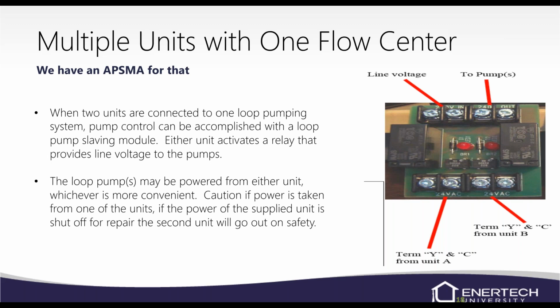Now, let's say that unit A is the one that's supplying the high voltage to the pump sharing module. If unit A goes down and you're out there working on it, and you kill the high voltage power, and then the second unit faults out on flow, well, that's because it's lost the high voltage and it's not turning your flow center pump on. So if you're working on one, it could actually affect the other unit as well. So just keep in mind that if you do have this, the high voltage is only supplied from one of the units, not both of them.